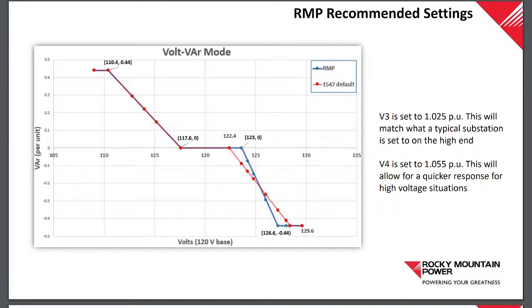So it's pretty similar. We discussed this with other utilities. Idaho Power has something, they go a little bit further out than what we're doing, and I think they were following some New York utilities and their deal. So it seems to me like it's a common practice to stay with the default settings on the lower voltage side of the IEEE standard, and then pinpoint or get into the details on the higher voltage, how you set your voltage settings. So that's what that slide's going over.